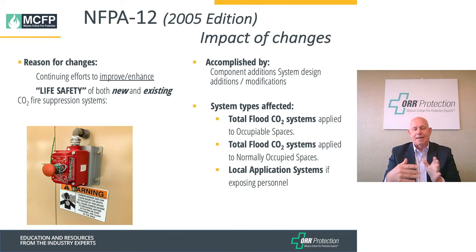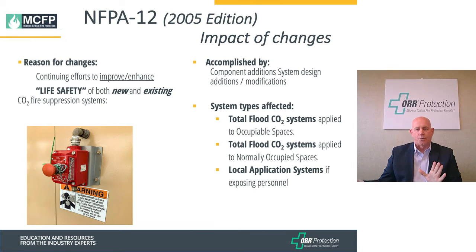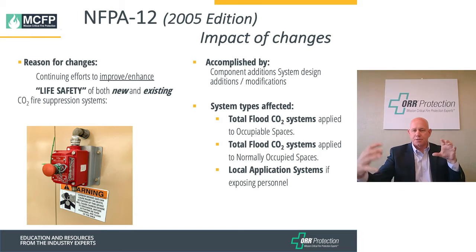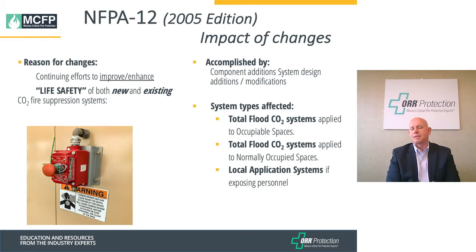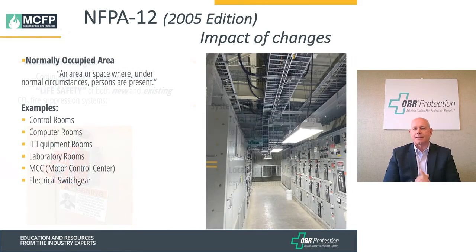Total flood systems apply to occupiable spaces and normally occupied spaces — key terms. Local application can be a quench tank, dip tank, hood system, wet bench, or paint booth. A roll mill in a steel factory is another local application, where we protect only the roll mill area as steel moves across a conveyor. CO2 migration and life safety come into play with local application as well, and NFPA 12 covers that.